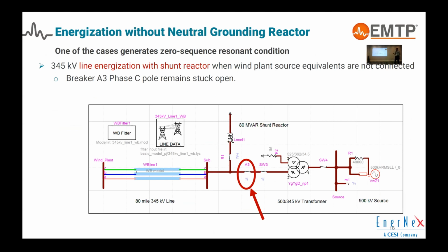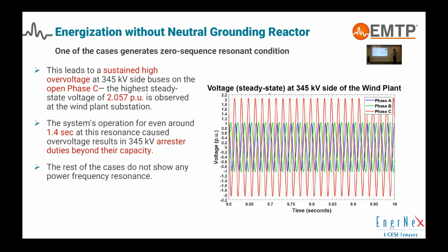Yep, so one of the cases that generated the zero sequence resonance condition in our circuit was when we energized this 80-mile line along with this shunt reactor using this breaker, and one of the poles remained stuck. In our simulation, we assume that phase C is stuck. I will move on to the next slide.